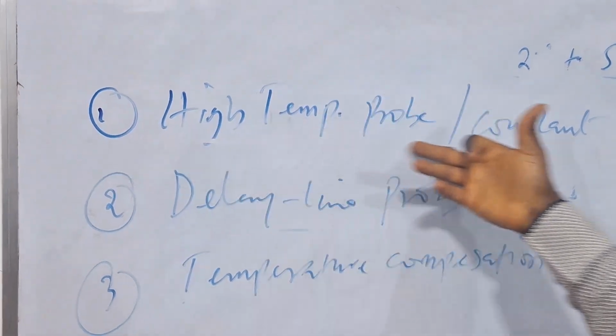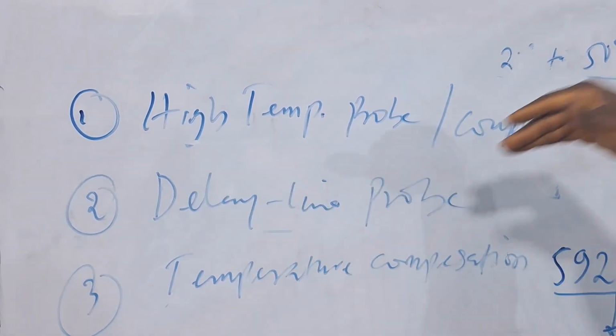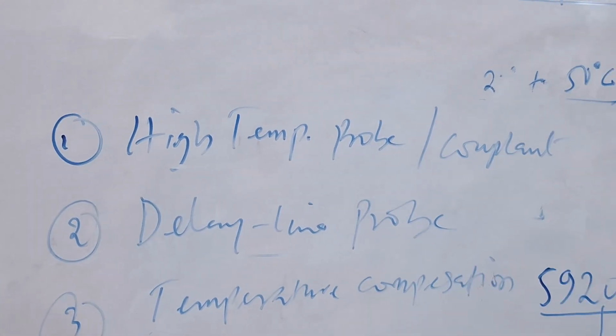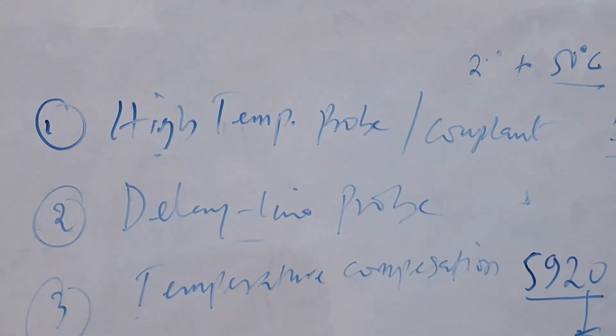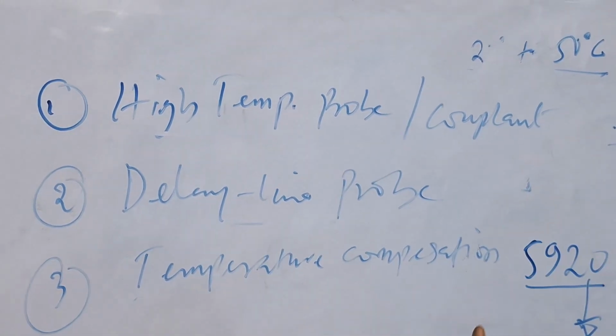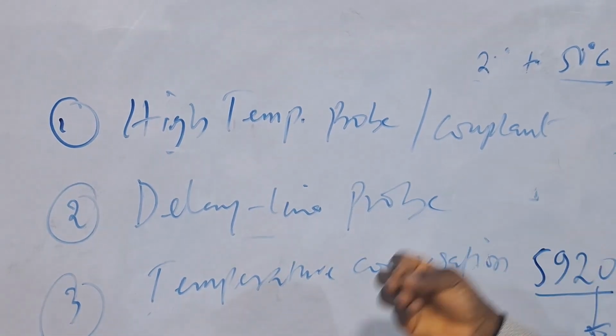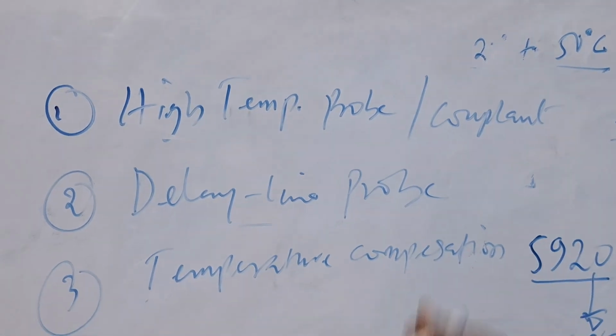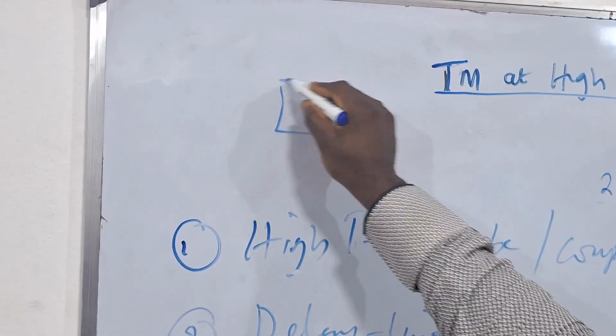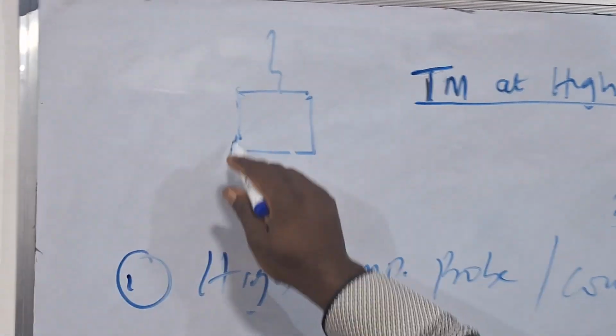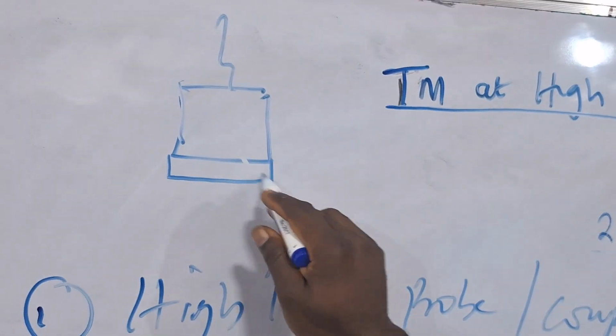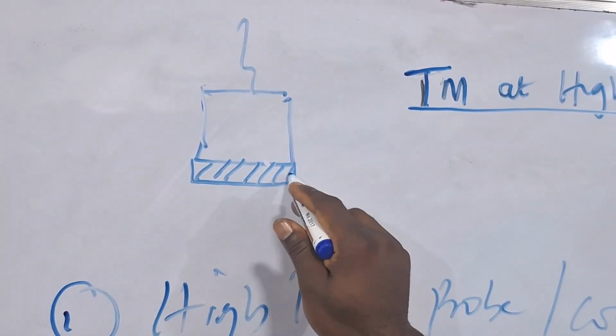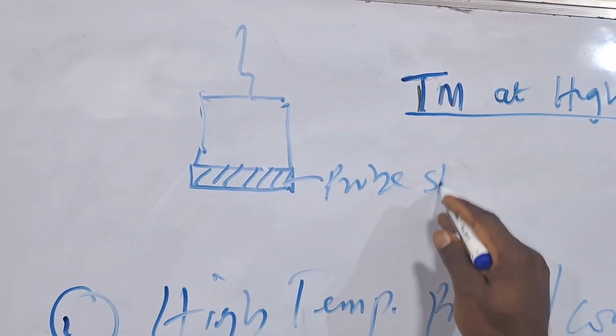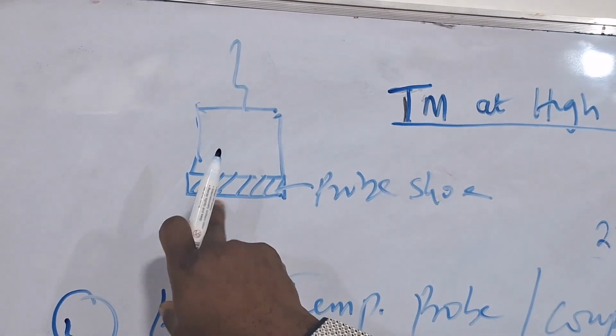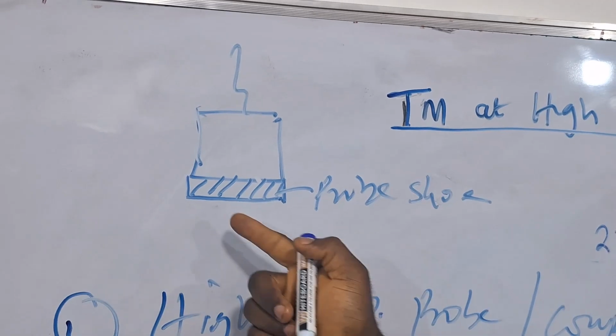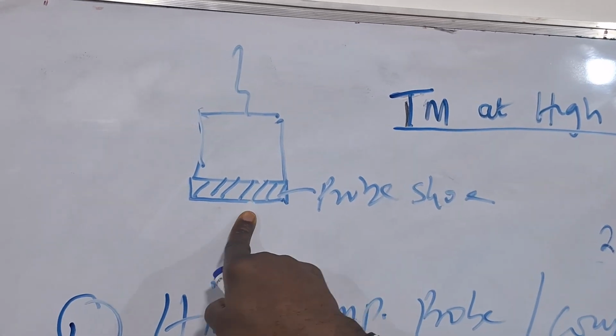So for the first one, we have our high temperature probe and couplant. In this case, if you have a very hot surface and you want to perform thickness measurement, you look for a probe that is able to withstand high temperature. By design, if this is your typical probe, so this is your probe housing, normally you will have an external protection for the probe, which is called your probe shoe. These parts can wear off easily, and when the temperature becomes very high, can also melt.